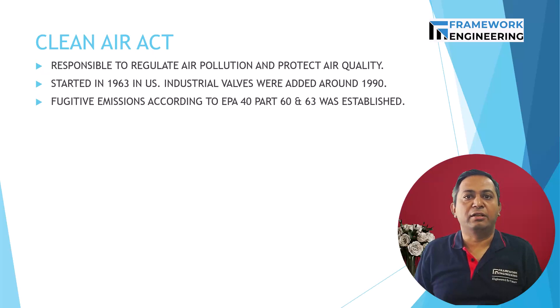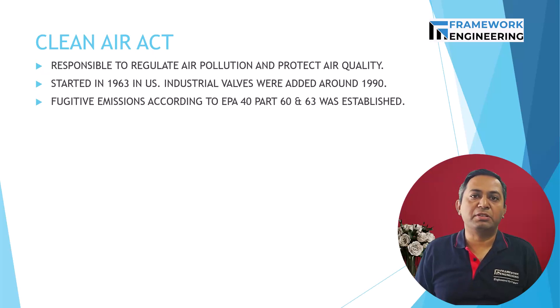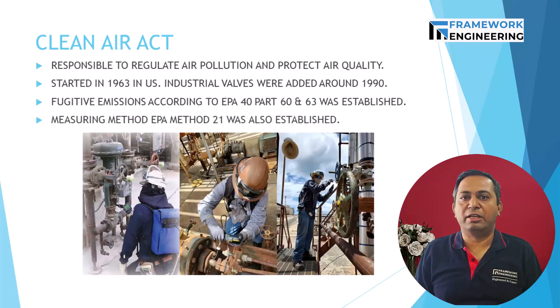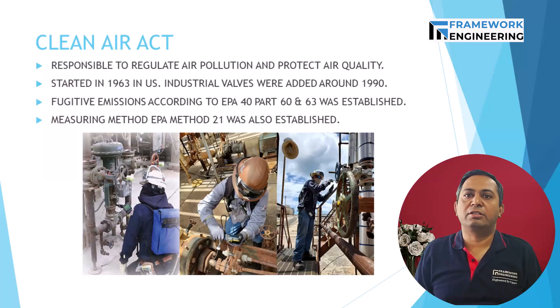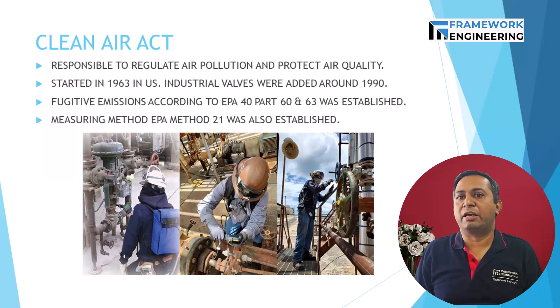Fugitive emissions are unintended releases of gases or vapors from valves, flanges, connectors, pumps, and other equipment in industries such as chemical manufacturing, petroleum, and oil and gas production. These emissions can contribute to air pollution and have adverse effects on human health and the environment. EPA Method 21 uses a portable organic vapor analyzer that is capable of detecting and quantifying VOCs in the ambient air.